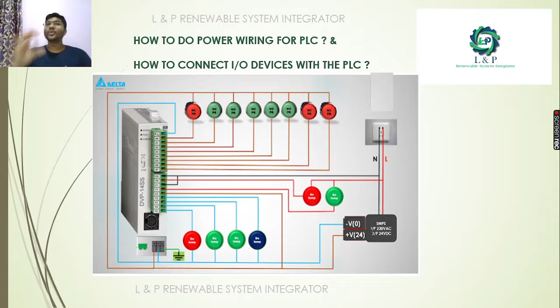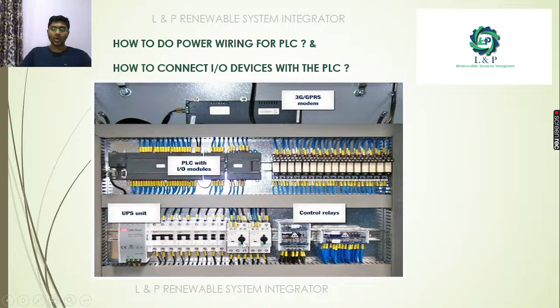Once everything is designed, we install it inside the control panel using the back plate. This is the PLC, this is the SMPS, and here all the outputs, normally digital outputs, we try to enable through control relays. For heaters and fans, heavy equipment running on a 230 volt supply, we use contactors, and for all protection purposes we use MCBs. If you are connecting any digital inputs, we connect them through terminals with fuses. This is an example where a motor is connected to the PLC.